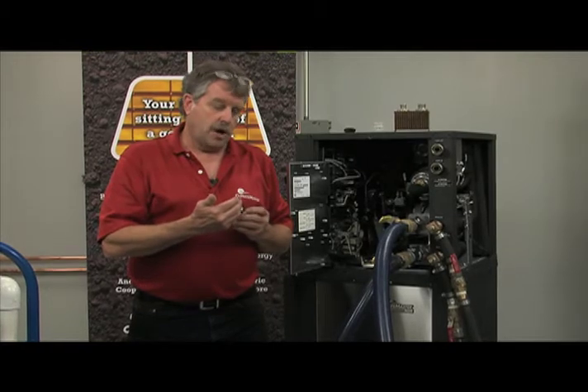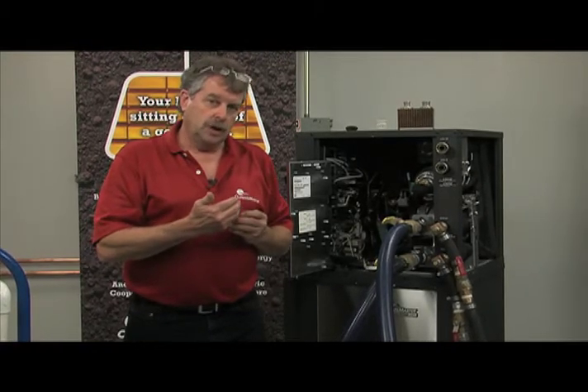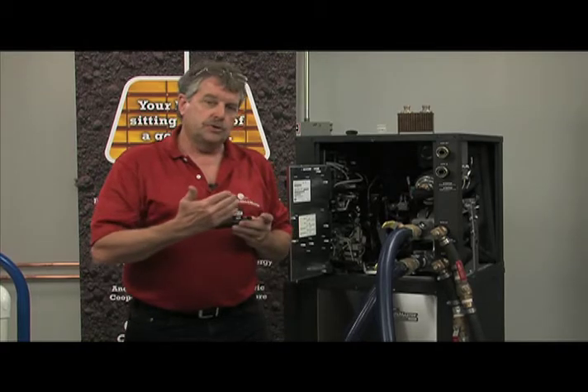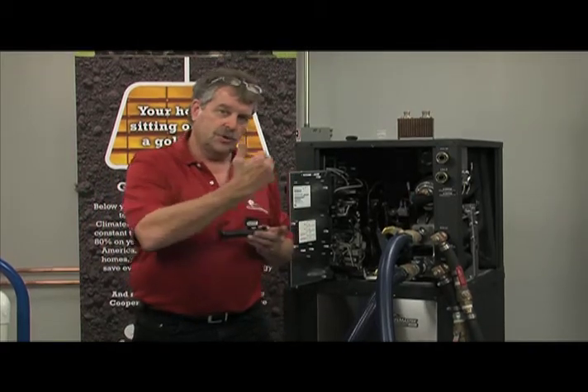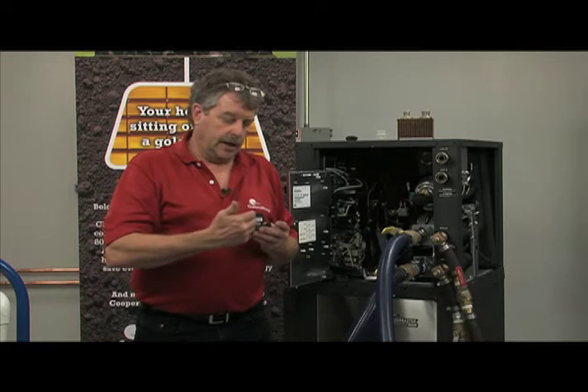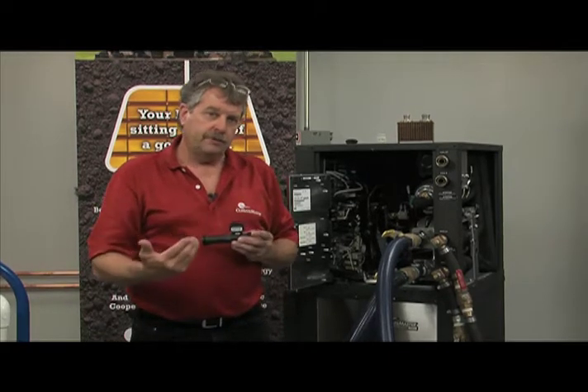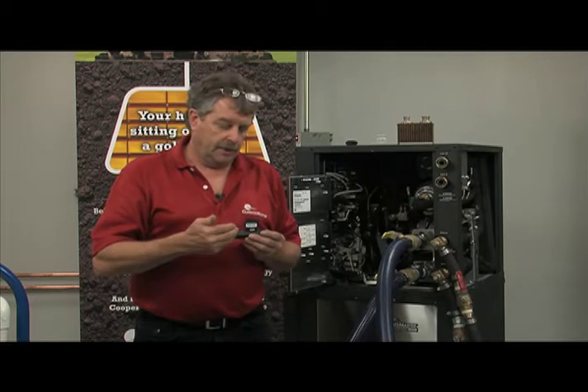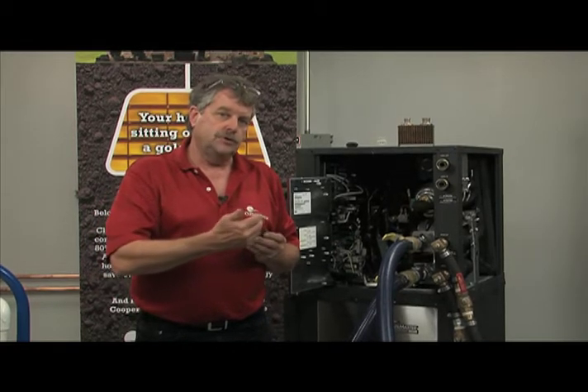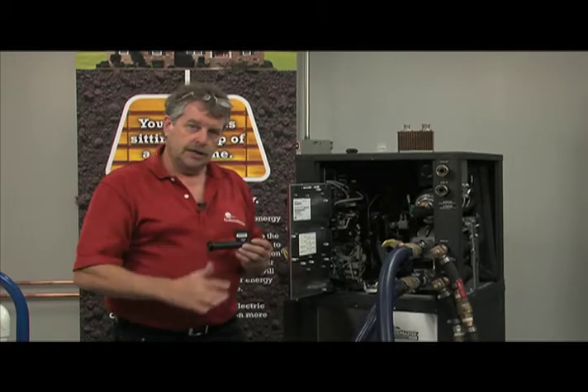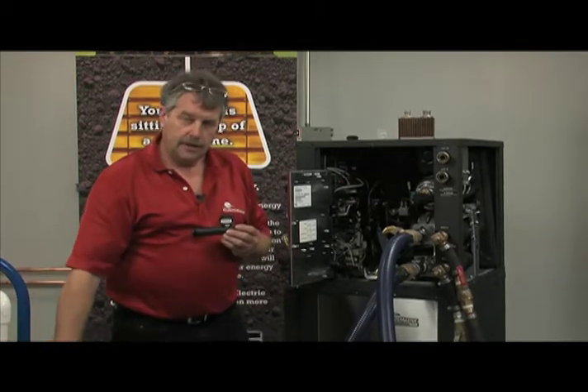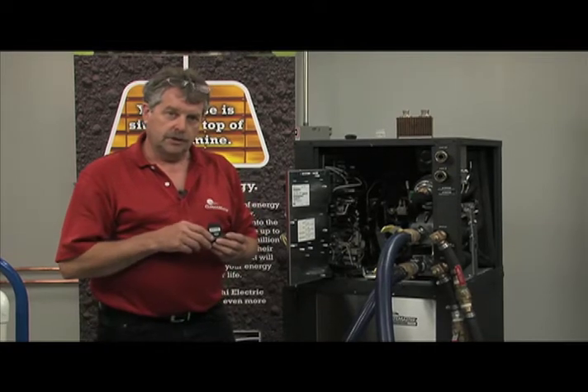So it's important to start out with a very modest flow and slowly flood, remove that cushion of air, slowly flood this heat exchanger as well as this flow meter, and get that pocket of air out of there, and then you can open up your flush cart to make sure you've removed all the air. But initially you need to slowly flood this unit and remove that pocket of air from behind the sensor so you don't compromise it through the flushing technique. So now it's time to rotate our built-in vFlow flush ports over to the unit side. Again, I have the flush cart shut off, and I have the return line also isolated on that valve.